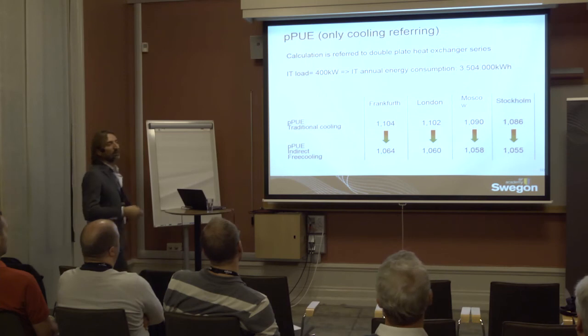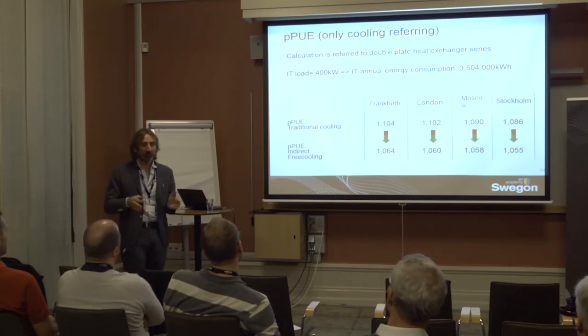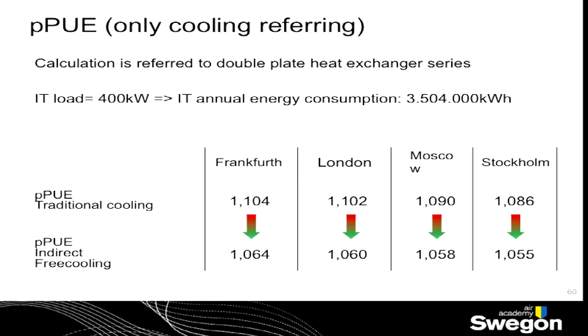Nothing more than this. So, in a system like this one, if we consider the partial PUE with a traditional cooling, when I say traditional cooling, I mean the most efficient water-free cooling system that we can provide today. So, a traditional cooling is a little bit tricky, probably. But compared with the partial PUE of an indirect free cooling system, we have a decrease of the partial PUE, of course. And if you think it is not so much, probably if you consider it in terms of energy saving for every one of these systems, you are going to change your mind, because you are going to save more or less 40% of the energy spent for cooling, going from probably the most efficient system that realizes a very high partial PUE.